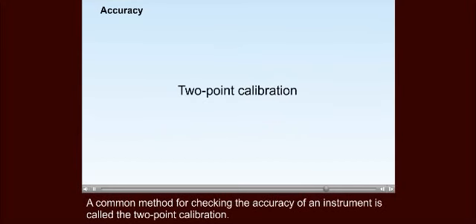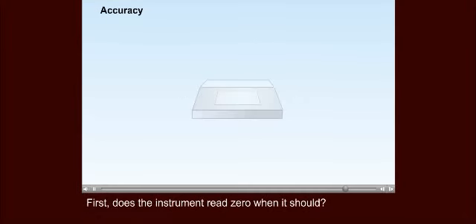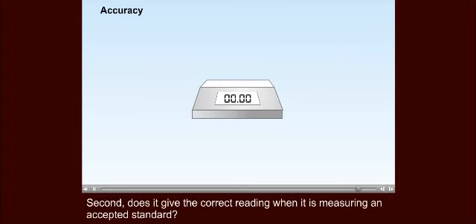A common method for checking the accuracy of an instrument is called the two-point calibration. First, does the instrument read 0 when it should? Second, does it give the correct reading when it is measuring an accepted standard?